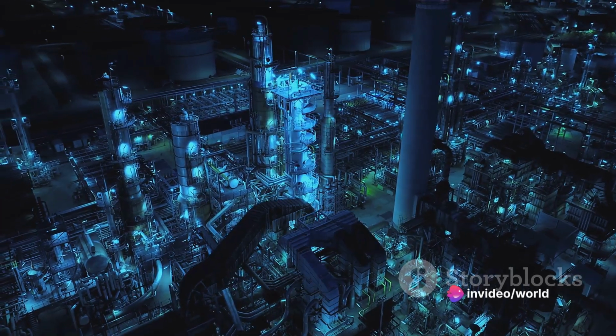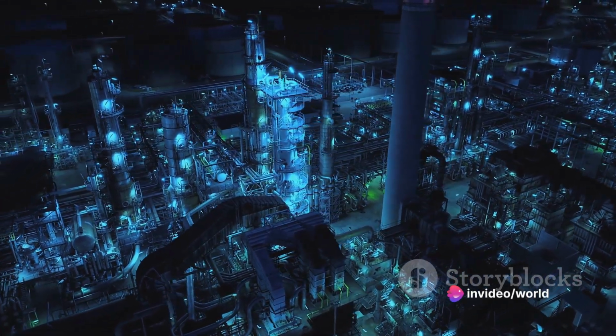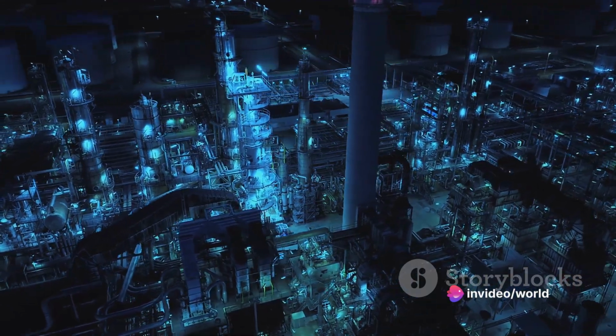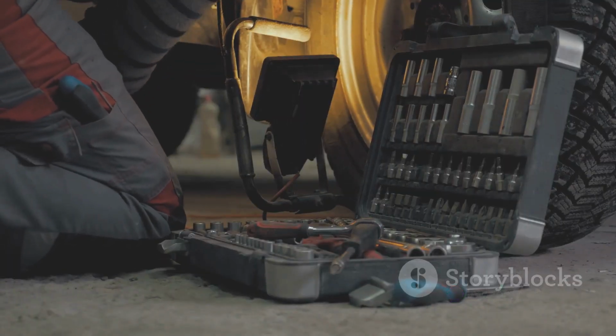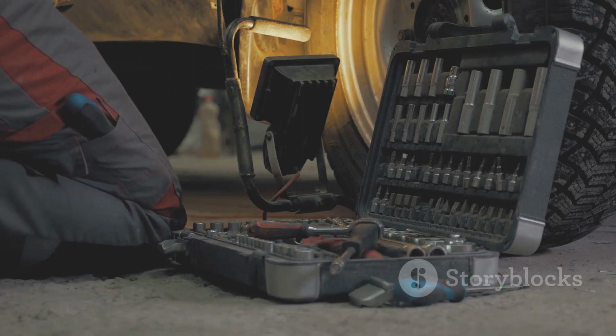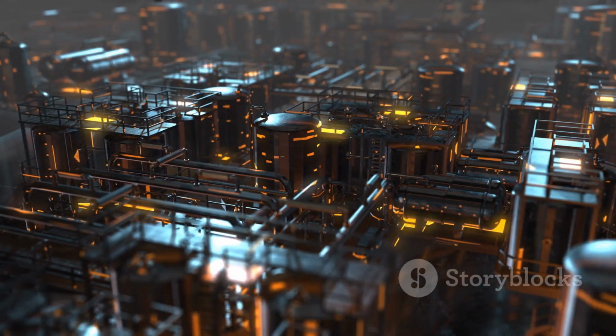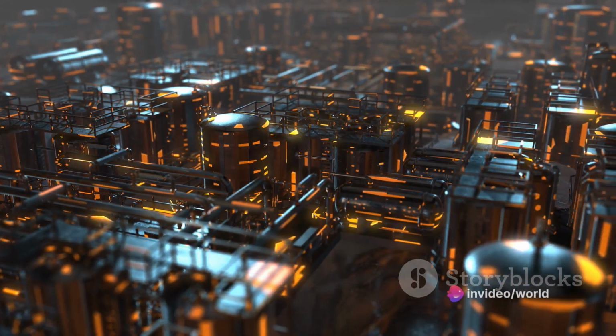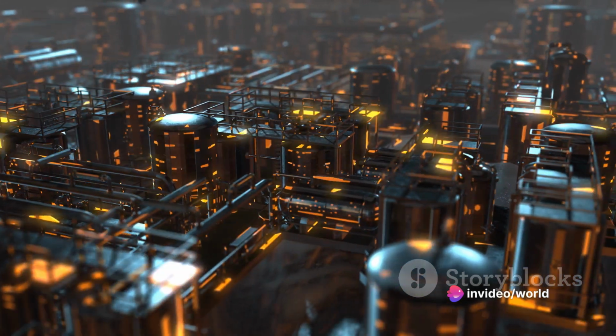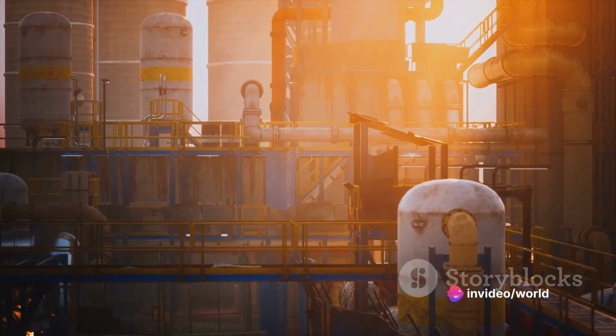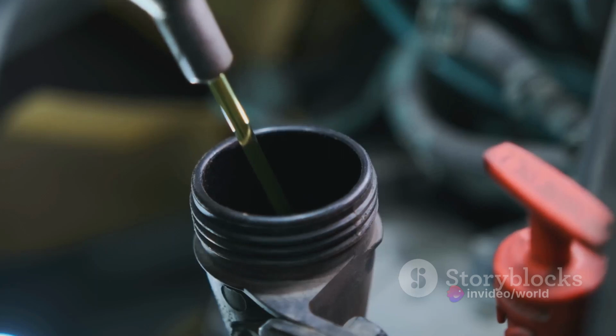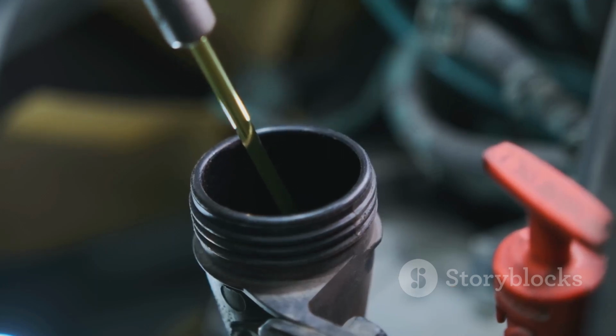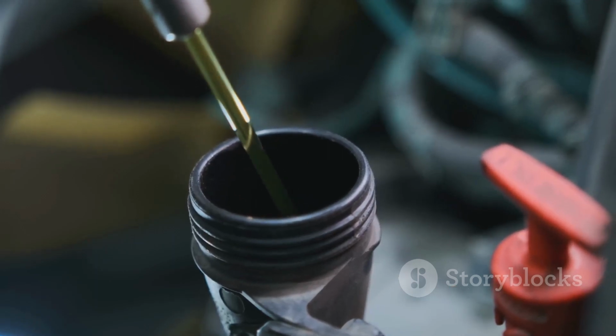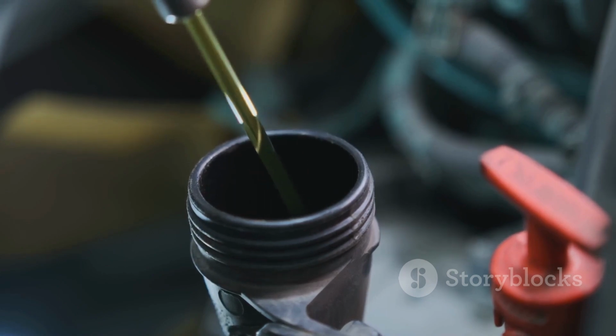Now let's shift our attention to the conservator, the transformer's very own oil regulator. In larger transformers filled with insulating oil, maintaining a constant oil level is crucial. The conservator, acting like a reservoir, is connected to the transformer tank via a pipe. As the oil expands and contracts with temperature changes, it moves in and out of the conservator. This ensures a consistent oil level, keeping the transformer functioning at its best. And so we've breathed life into our understanding of transformers from the core to the conservator.